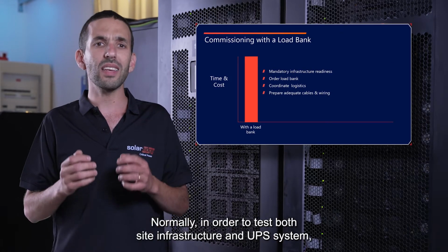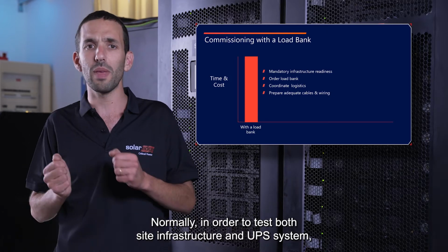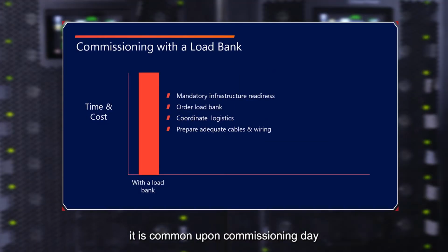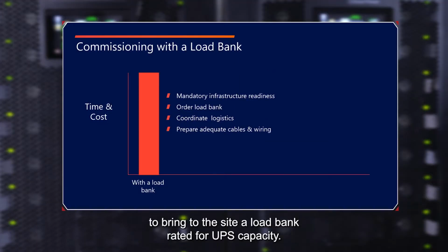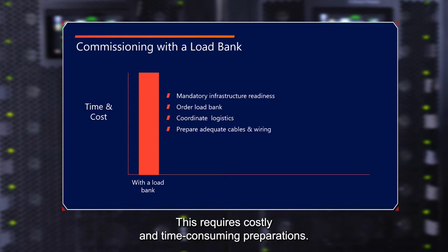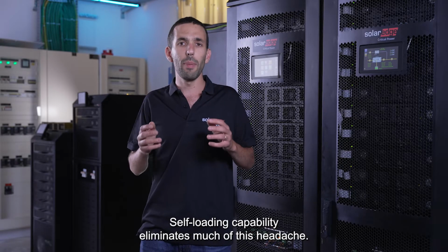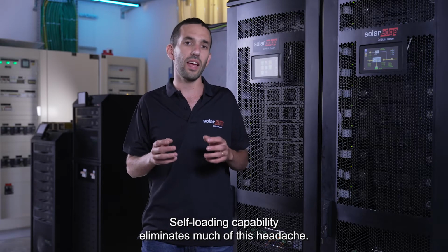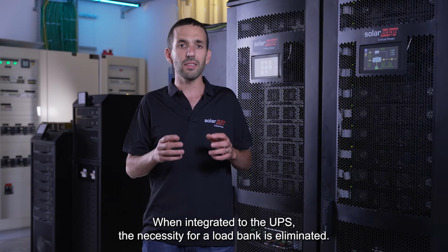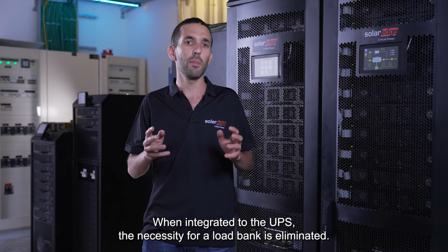Normally, in order to test both site infrastructure and UPS system, it is common upon commissioning day to bring to the site a load bank rated for UPS capacity. This requires costly and time-consuming preparations. Self-loading capability eliminates much of this headache. When integrated to the UPS, the necessity for a load bank is eliminated.